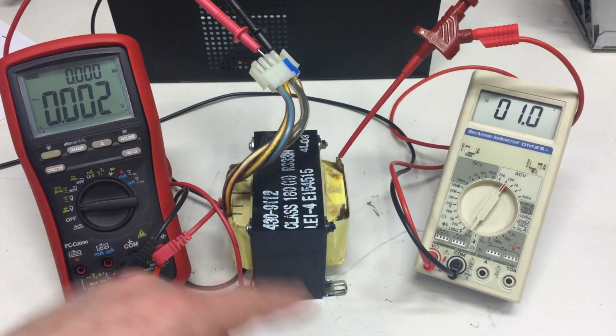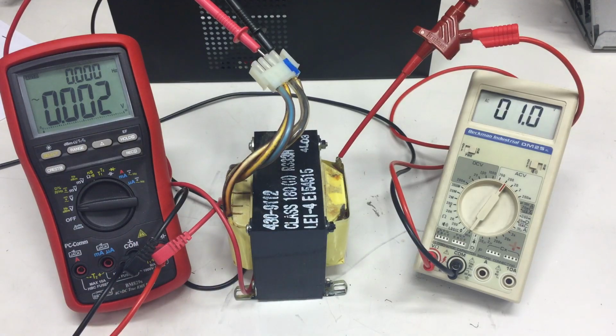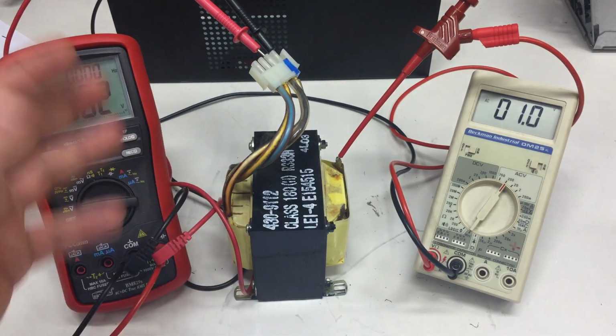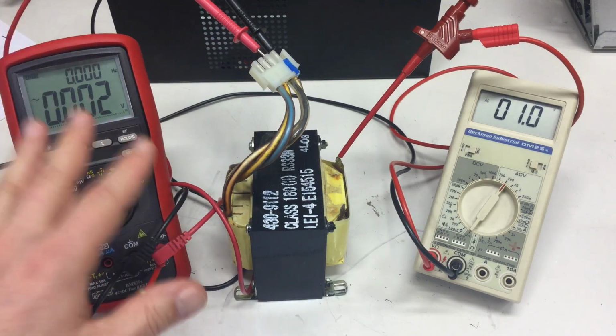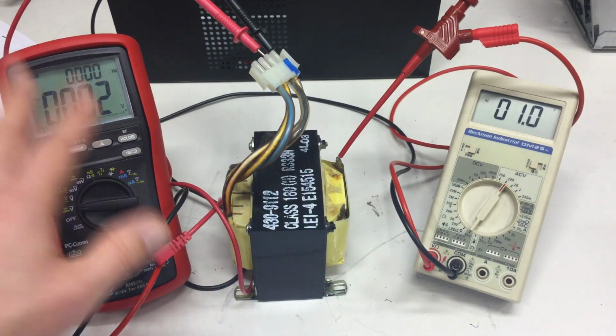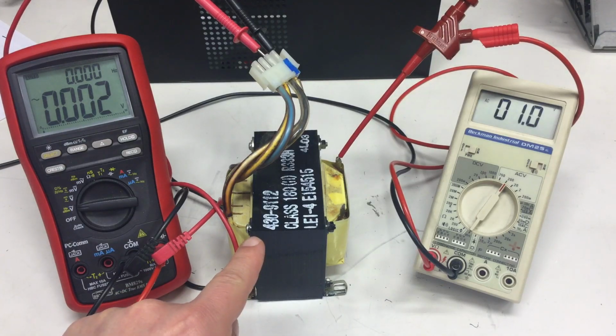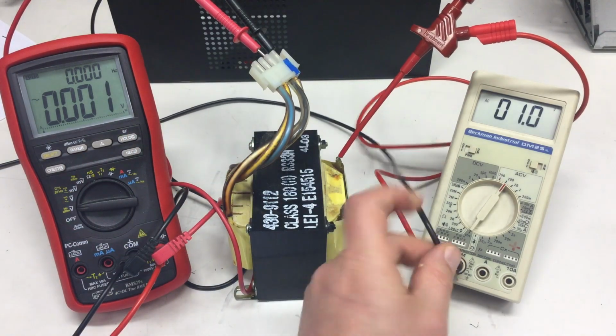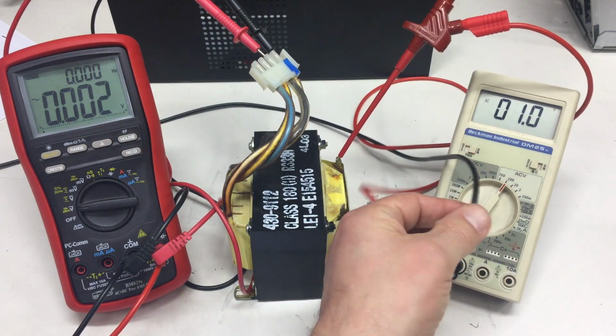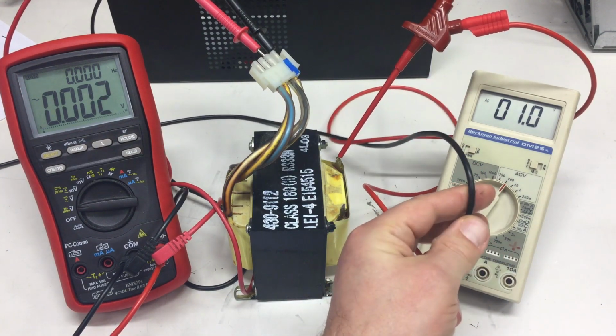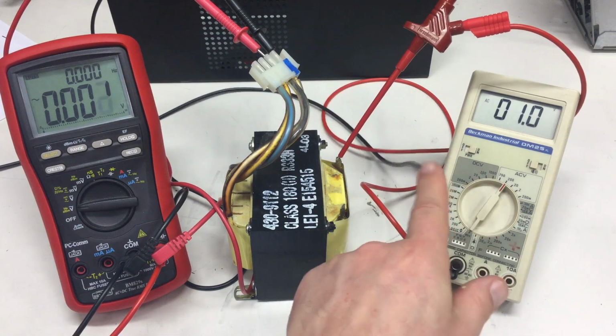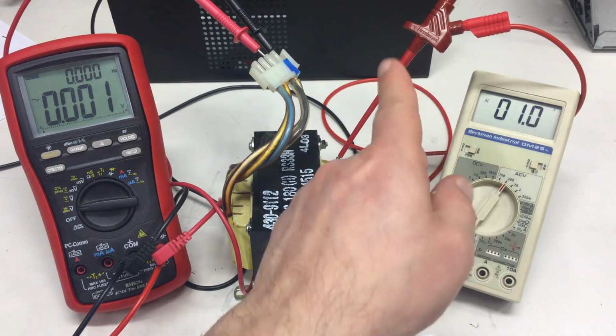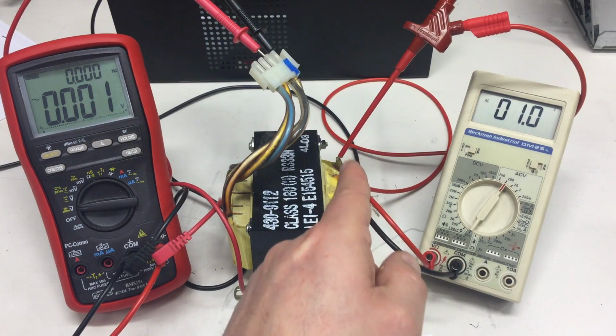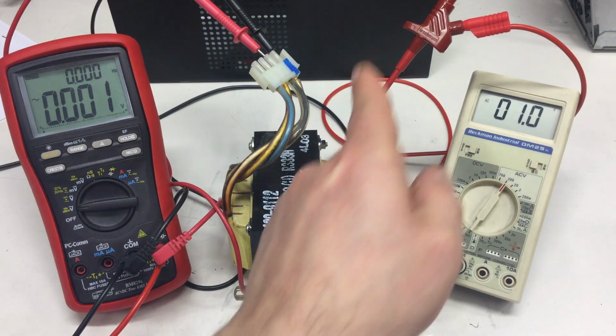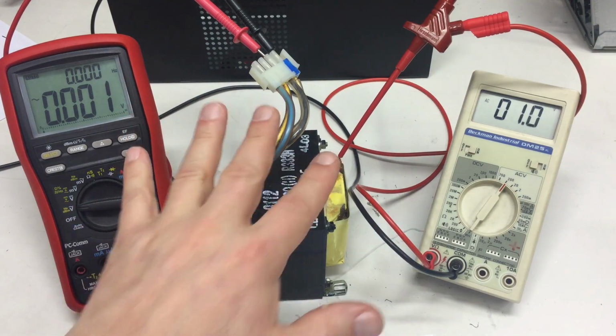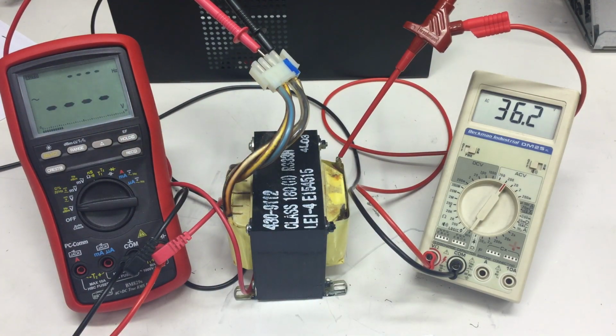So I said in the beginning the isolation tests I did with just the ohmmeter here don't are an indication, but don't prove anything because these are really low voltage tests. What I now do is, yeah, this is on volts AC, and this buggers off to mains earth. And so I'm measuring basically, can I get a voltage between the secondary and mains earth when I power this up, which I will do now.